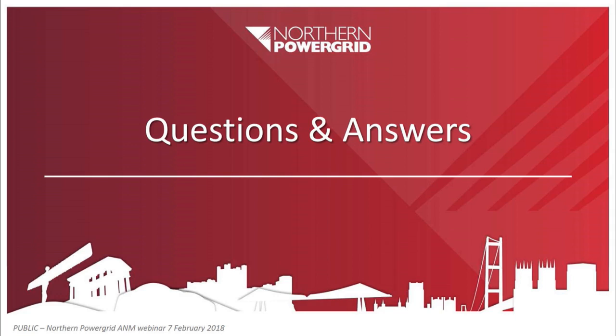So obviously there's a limited thermal inertia capability in overhead lines that we might be able to exploit slightly, but the actual target set points will be set to keep generators down below the post-fault power flows that could occur, and that also goes for the transformers that we've got at Driffield. So say if we have two 90 MVA rated capacity transformers at Driffield, the power flows will be limited to 90 MVA. So we've got 180 MVA worth of capacity, but we'll be limiting to around 90 MVA in theory, and that's pre-fault. And that's effectively what we do for demand. It's just treating the generation the same way as we would treat a demand customer to maintain security of supply to all the other customers that are connected to the Driffield network.